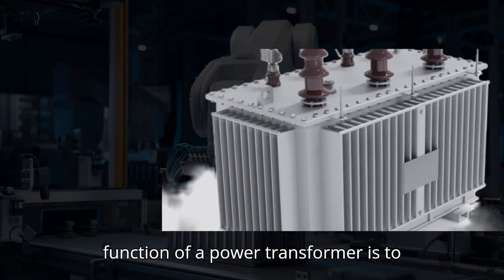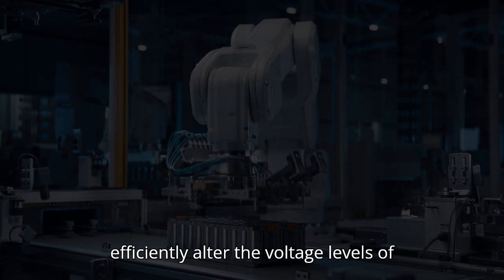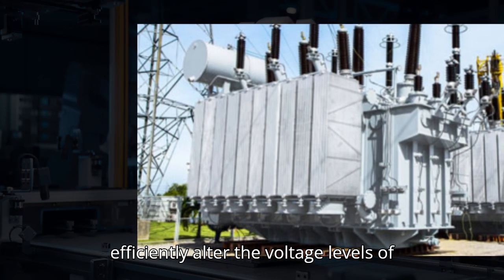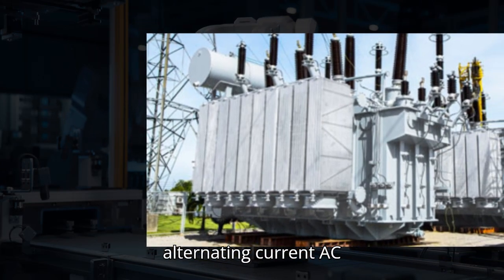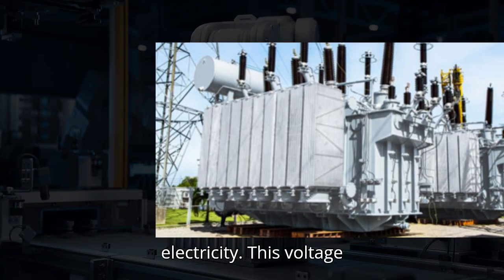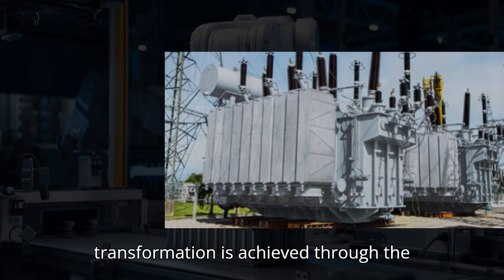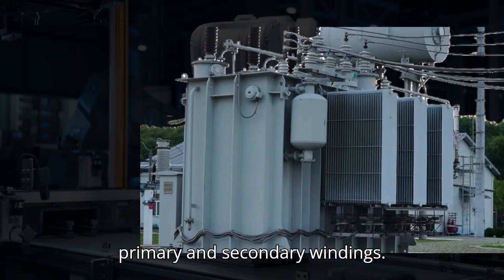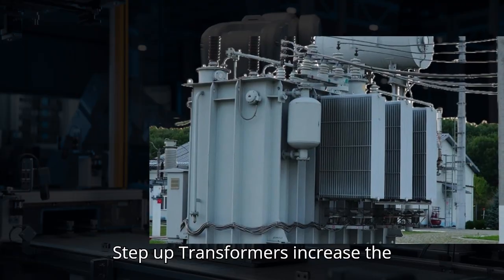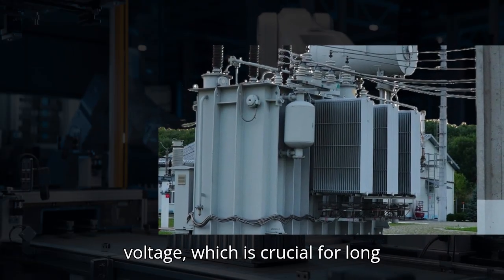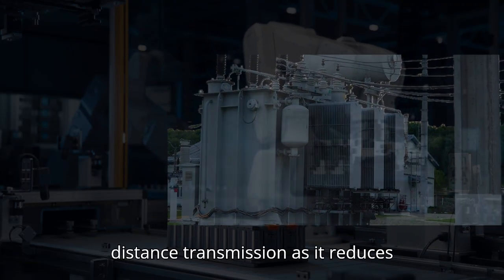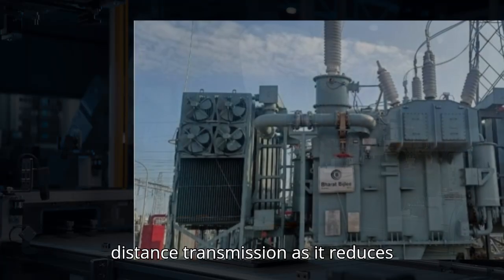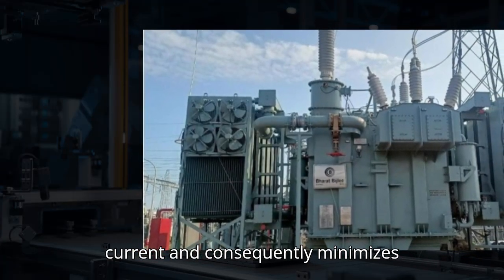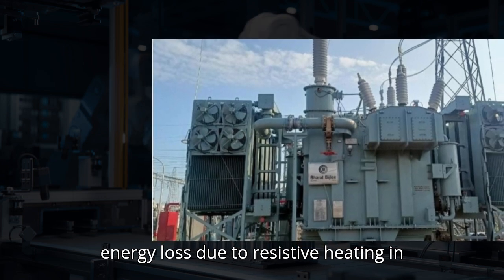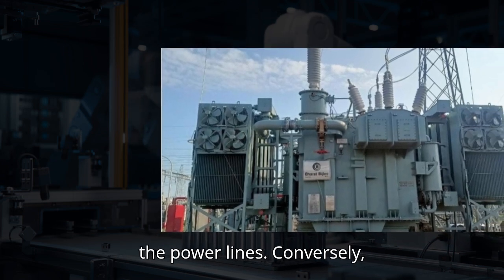The primary function of a power transformer is to efficiently alter the voltage levels of alternating current, AC, electricity. This voltage transformation is achieved through the ratio of the number of turns in the primary and secondary windings. Step-up transformers increase the voltage, which is crucial for long-distance transmission as it reduces current and consequently minimizes energy loss due to resistive heating in the power lines.